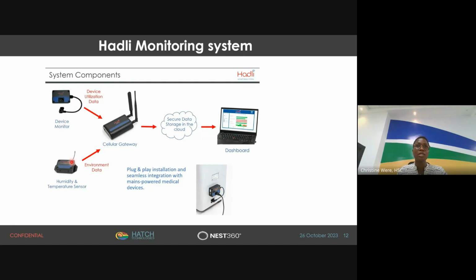Since we're dealing with the newborn unit (NBU), we want to measure the humidity and temperature of that room, so there's also a very small sensor for humidity and temperature measurements. These two sensors collect data on utilization, whether the machine has been switched on or not. Specifically, the device monitor collects data to know whether current is flowing to the machine, showing whether it has been switched on or not.